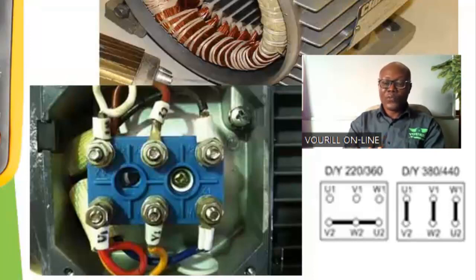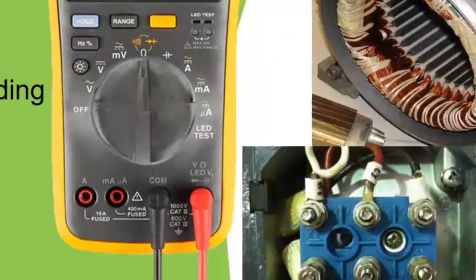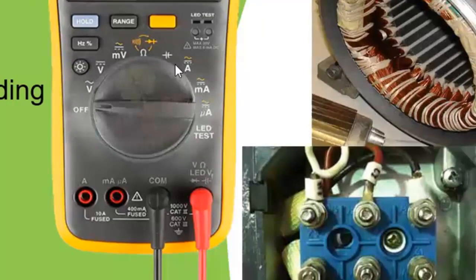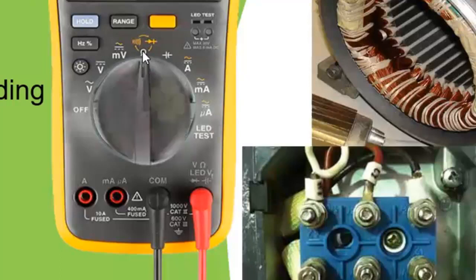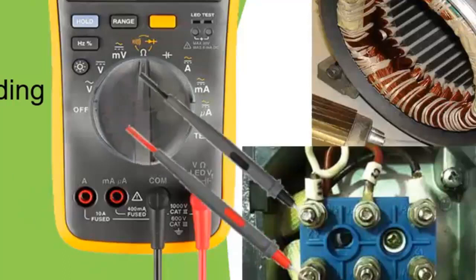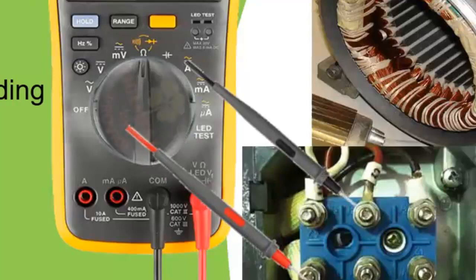So you continue for V and W to ascertain which of the windings is actually causing the problem, and also know which of the windings is open. What you do first, you switch the digital multimeter to the continuity selection. As you can see, it is now on continuity. You take the red probe to U1, and the other to U2. If it is continuous, you will hear the beep. But if it is broken, that is, there is an open circuit in that winding, you will not hear any beep. You will see an overload, telling you that the circuit is open. So you immediately know that that U winding is faulty. If it is okay, you will hear that beep. Remember, you are testing continuity.